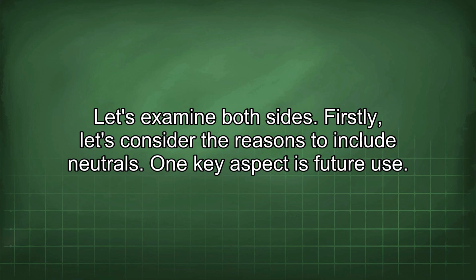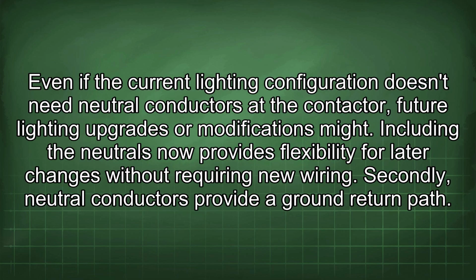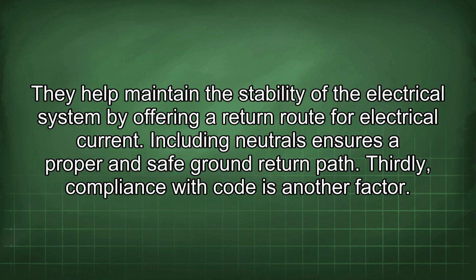One key aspect is future use. Even if the current lighting configuration doesn't need neutral conductors at the contactor, future lighting upgrades or modifications might. Including the neutrals now provides flexibility for later changes without requiring new wiring. Secondly, neutral conductors provide a ground return path. They help maintain the stability of the electrical system by offering a return route for electrical current. Including neutrals ensures a proper and safe ground return path.